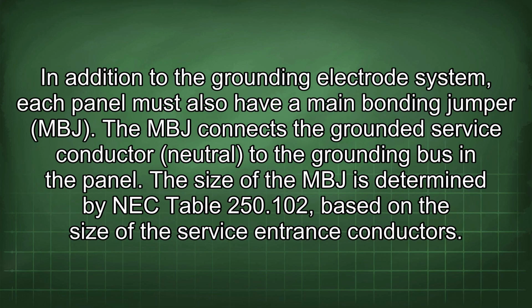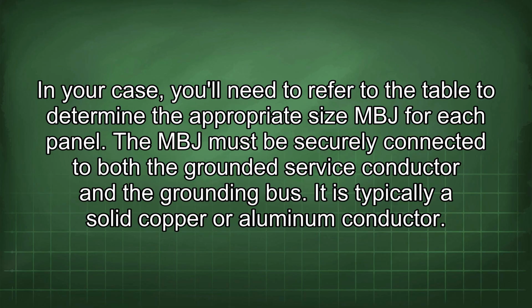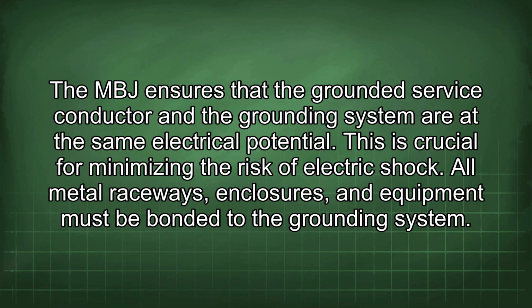In addition to the grounding electrode system, each panel must also have a main bonding jumper, MBJ. The MBJ connects the grounded service conductor, neutral, to the grounding bus in the panel. The size of the MBJ is determined by NEC table 250.102 based on the size of the service entrance conductors. In your case, you will need to refer to the table to determine the appropriate size MBJ for each panel. The MBJ must be securely connected to both the grounded service conductor and the grounding bus. It is typically a solid copper or aluminum conductor. The MBJ ensures that the grounded service conductor and the grounding system are at the same electrical potential. This is crucial for minimizing the risk of electric shock.